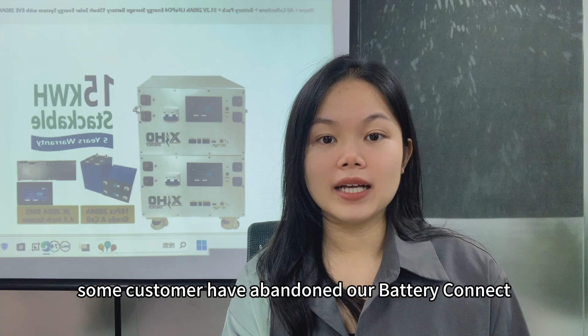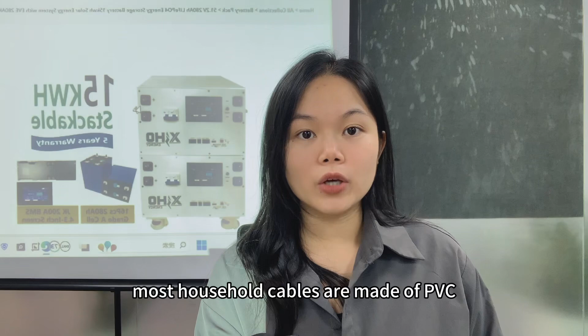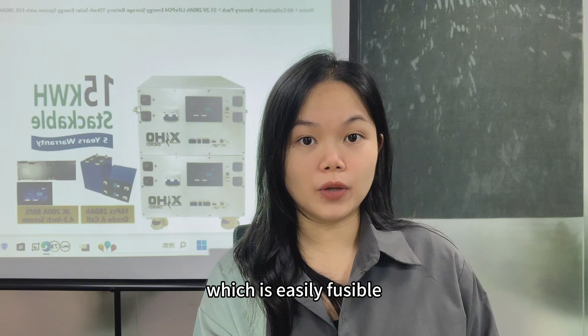And the fourth point, using ordinary wires instead of a battery bus bar. Some customers have abandoned our battery connectors and used 14 AWG household cables to connect a 48 volt 100 ampere battery pack under the current of 100 amp. The cable quickly melted and burned. Most household cables are made of PVC, which is easily fusible.